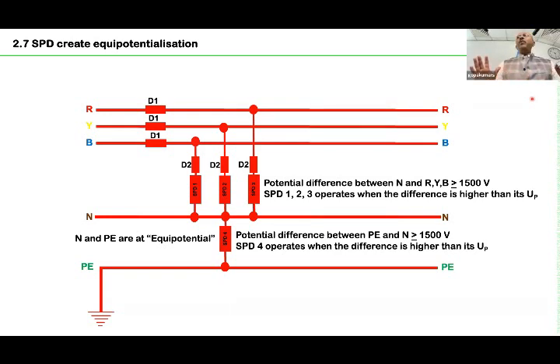Generally, if you have very good wiring from the distribution board up to your equipment, the length of the line, neutral and earth wire is similar. Sometimes the length is not similar. We really don't know. It depends on the quality of the workmanship or the quality of the electrician. In a good electrical installation, from the location of the SPD downstream, there is no potential difference. As a result, your equipment will not experience a voltage for a short time.